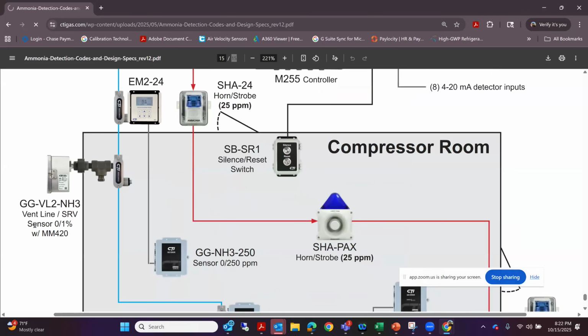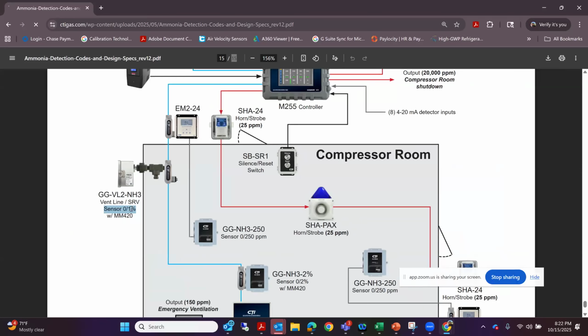This is 0 to 10,000, as you can see here. We're measuring 0 to 10,000. The alarm set point for this is usually right at 10,000, because as you can tell from that release a moment ago on the video, that's a lot higher than 10,000. And usually when these are going off, they're going off full scale. You're usually getting a pretty good stink coming out of those. And so the alarm set points are typically maybe a 5,000 warning, but usually it's a 10,000 ppm shutdown or pump down or trigger to the folks inside, saying, hey, this is our only alarm.